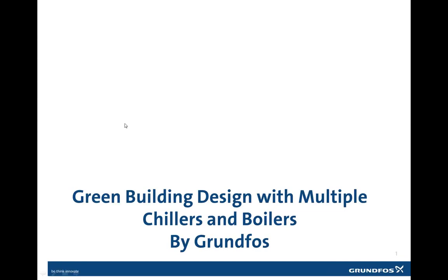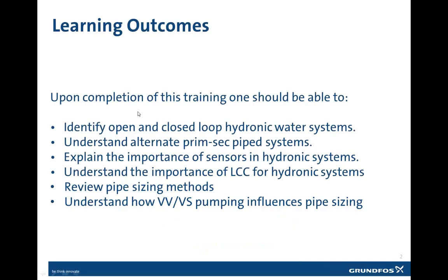So good morning. What we're going to discuss today is green building design with multiple chillers and boilers, and some of the best practices and considerations that we want to think about in designing for green building applications. Upon completion of the training, we should be able to identify the differences between open and closed loop hydronic water systems, understand some of the alternate primary, secondary pipe systems, explain the importance of where the sensors are located in hydronic systems, understand the importance of a life cycle cost analysis for hydronic systems, review some of the different piping methods, and also understand how variable volume, variable speed pumping influences pipe sizing.